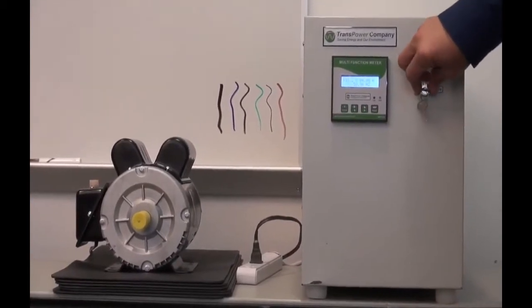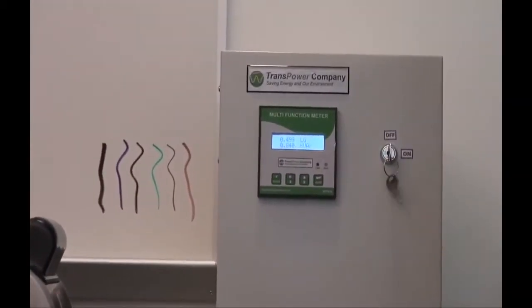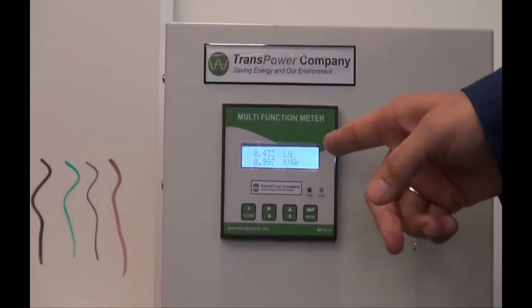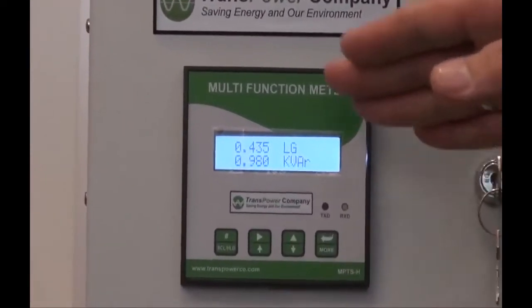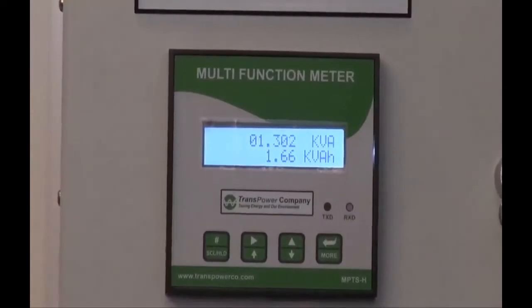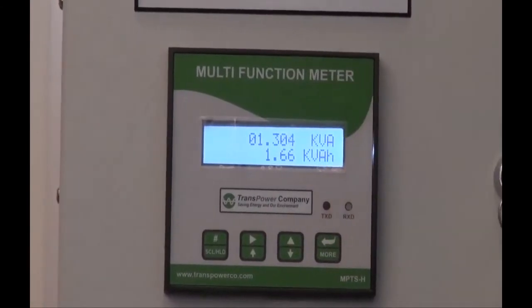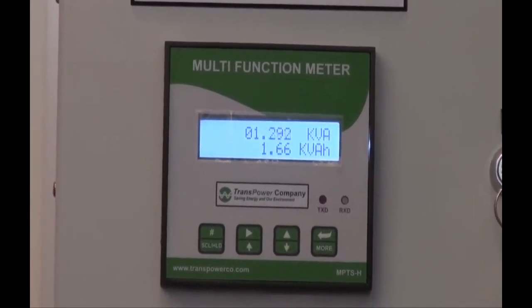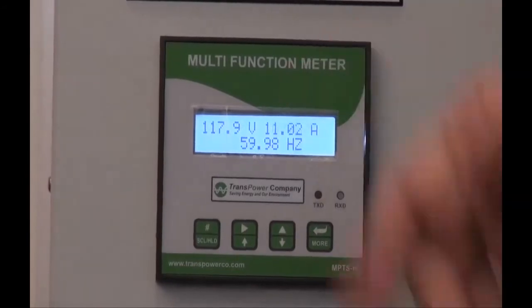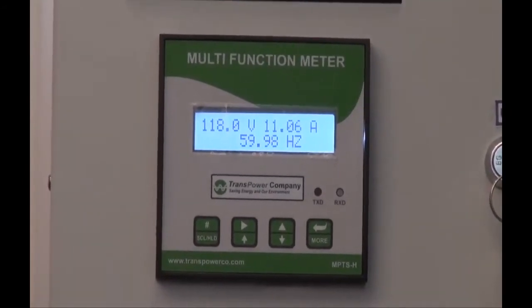Now, as I turn the equipment off, you'll see all the numbers immediately go right back up. The power factor goes from 0.98 down to 0.4. The kVA jumps up to 1.3 immediately, and the amps go back up to 11 just by turning it off.